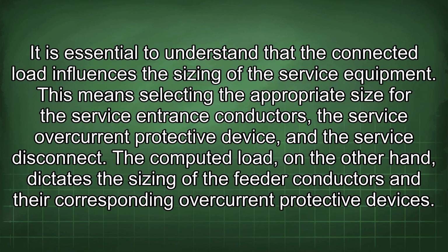It is essential to understand that the connected load influences the sizing of the service equipment. This means selecting the appropriate size for the service entrance conductors, the service overcurrent protective device, and the service disconnect. The computed load, on the other hand, dictates the sizing of the feeder conductors and their corresponding overcurrent protective devices.